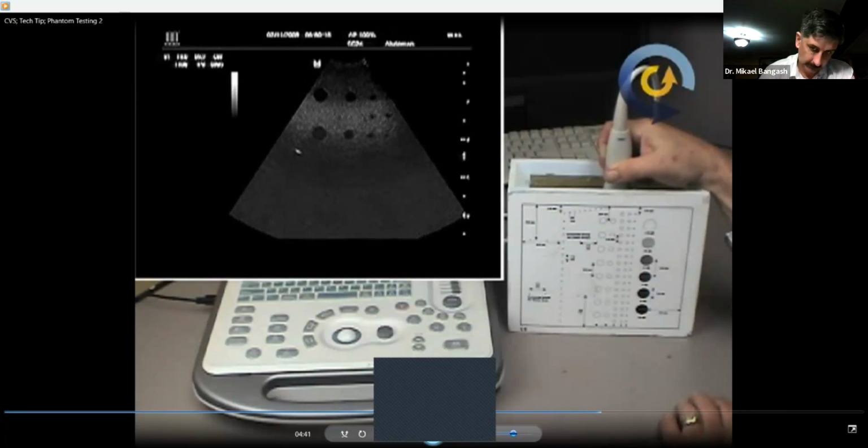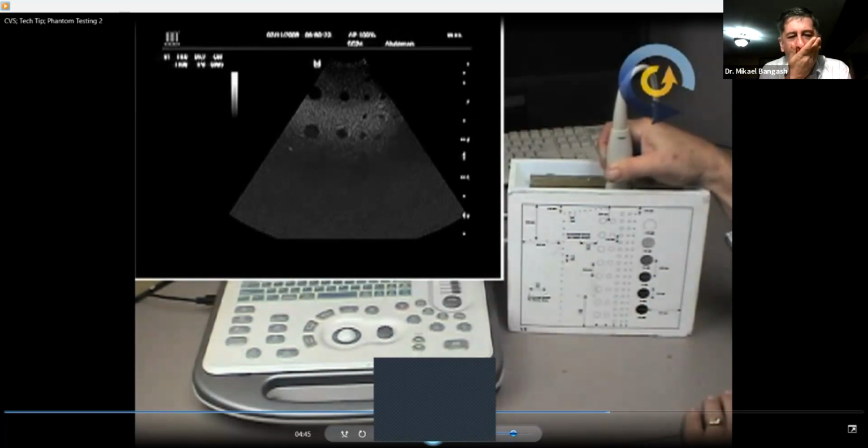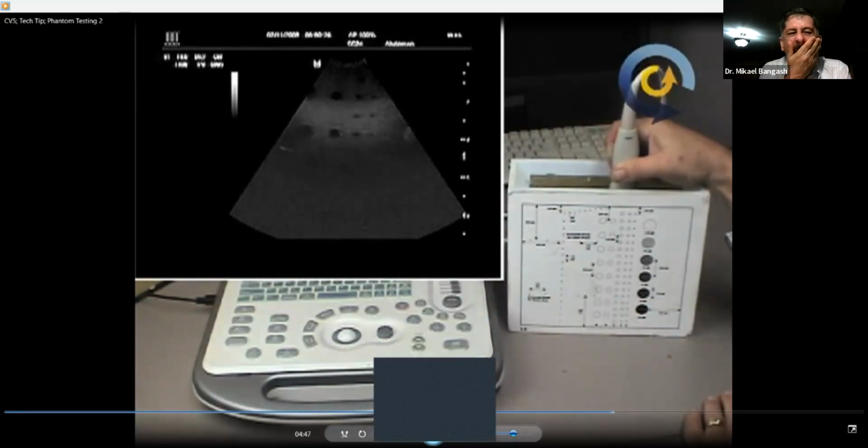Those are the most typical uses of an ultrasound phantom, and an ultrasound 2D grayscale phantom like this one, a tissue mimicking phantom, is by far the most common. I told you there are other phantoms, the ones I mentioned before, such as the breast, the prostate, and the head and neck. Those are just similar phantoms with a little different physical structure so that you can put a transducer that would be used for that.